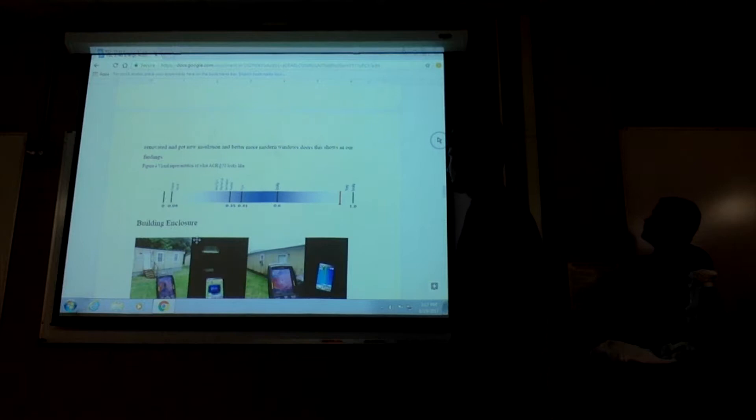We ran our test and we estimated that the volume of the house was 3,200 cubic feet. The first test ended up being an ACH50 of 32.81. Test two, we did a similar setup, but we tried to benefit the housing enclosure by putting towels around the AC unit, putting towels around the cracks of the doors, just trying to get as tight as possible. So we ran it again. We ended up getting a slightly better number. It was ACH50, which would be 30.94.